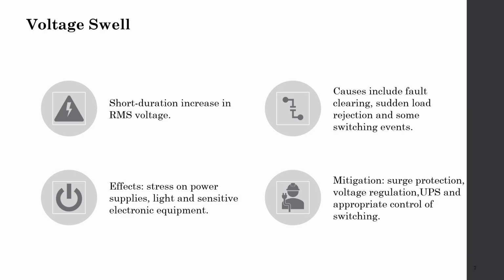Then we talk about voltage swell. Swell means a short duration increase in the RMS voltage. Causes include fault clearing, sudden load rejection, and some switching events. From this, we could affect stress on power supplies, lights, and sensitive electronic equipment. For mitigating this issue, we should use surge protectors, voltage regulation, UPS, and appropriate control of switching.